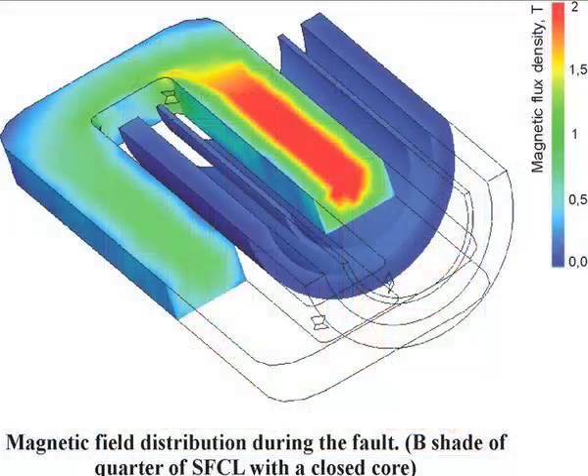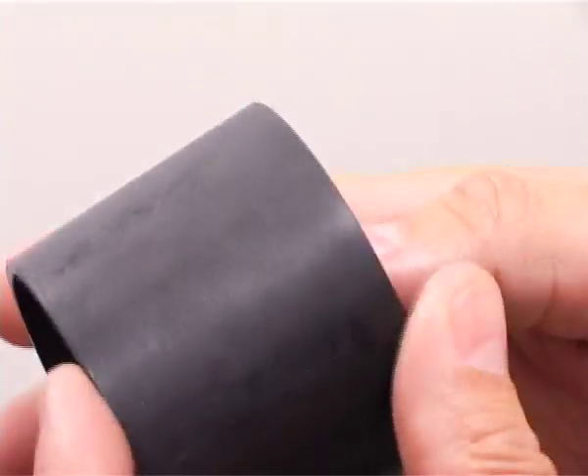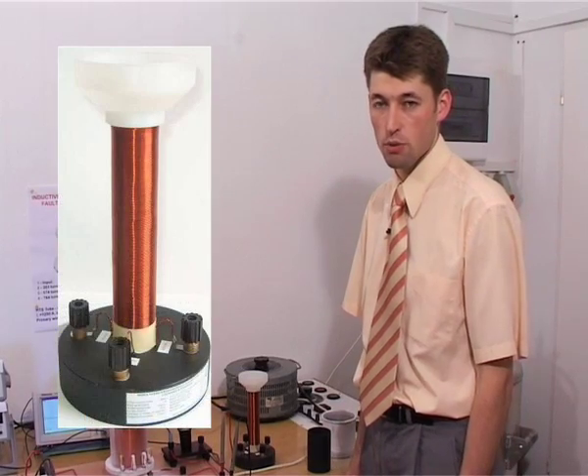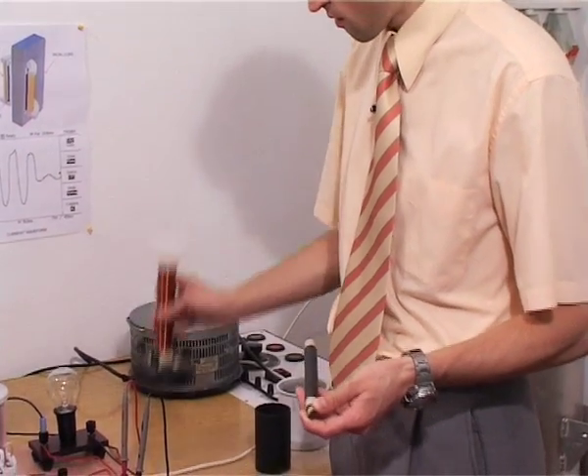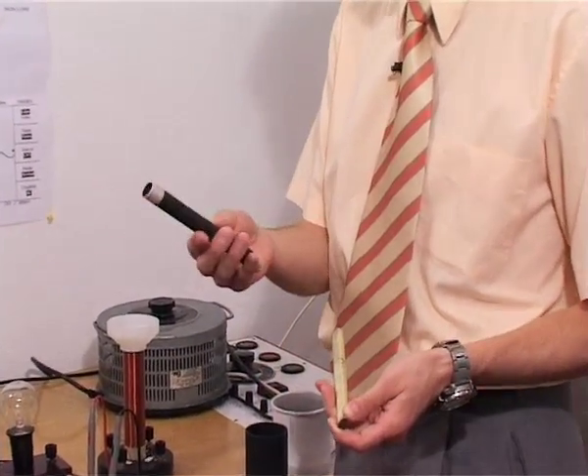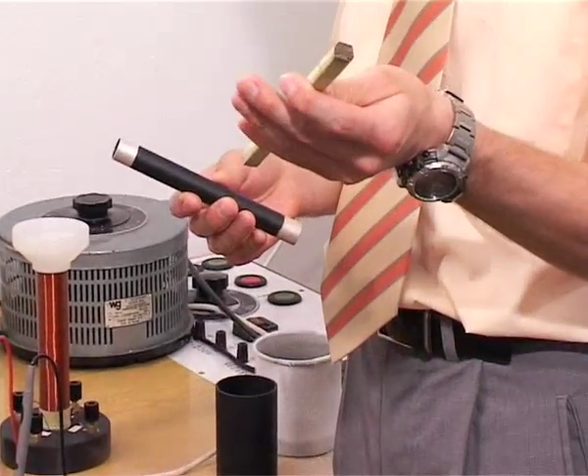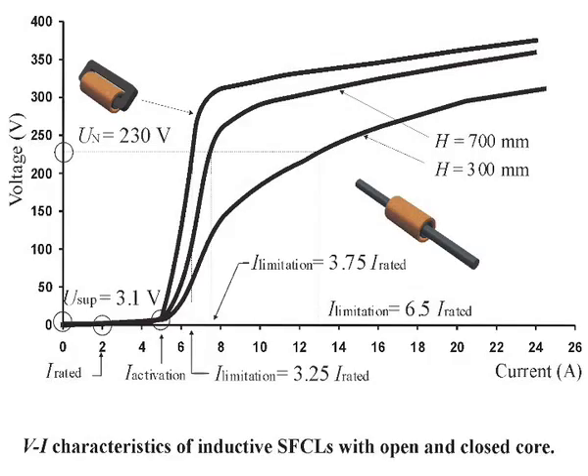Despite the fact that potential hot spots are easily bypassed in the superconducting cylinder of inductive fault current limiters, mechanical stress induced during a fault may cause fracture, breaking the continuity of the superconducting cylinder. The other type of superconducting fault current limiter is a limiter with an open core, which is simpler to service and simpler in structure. It has a primary copper winding, a secondary superconducting winding, and an iron core. The voltage-current characteristics of this type are not as good as the limiter with a closed core, and the efficiency of the open core limiter will never match that of the closed core limiter.